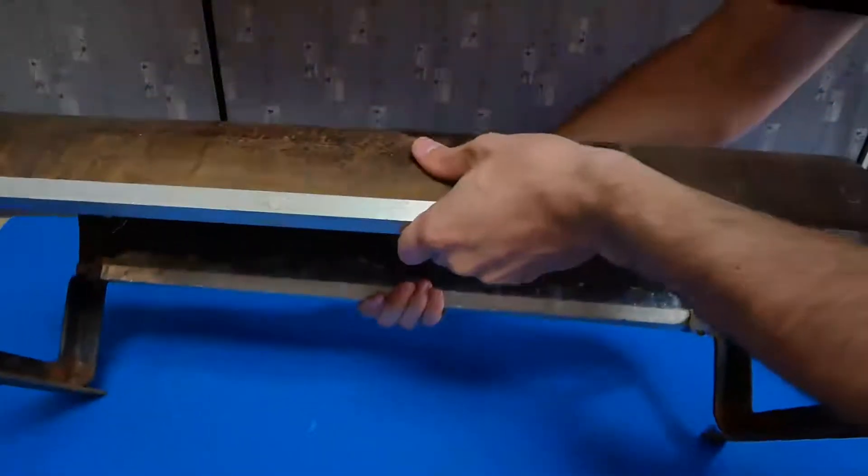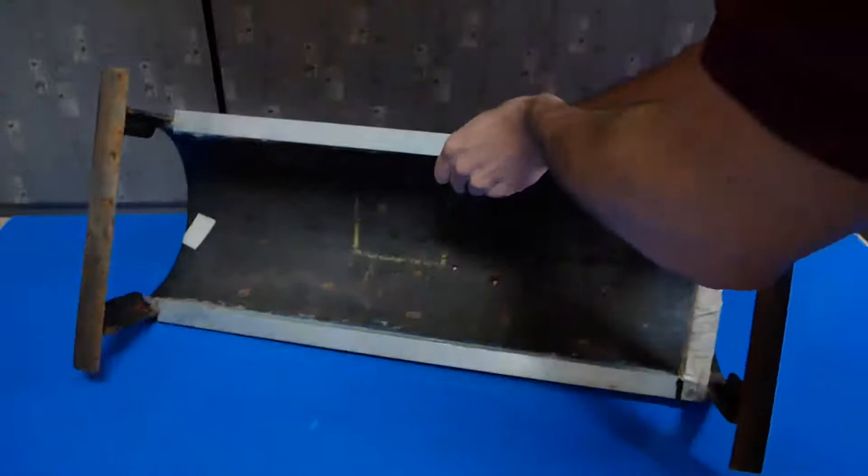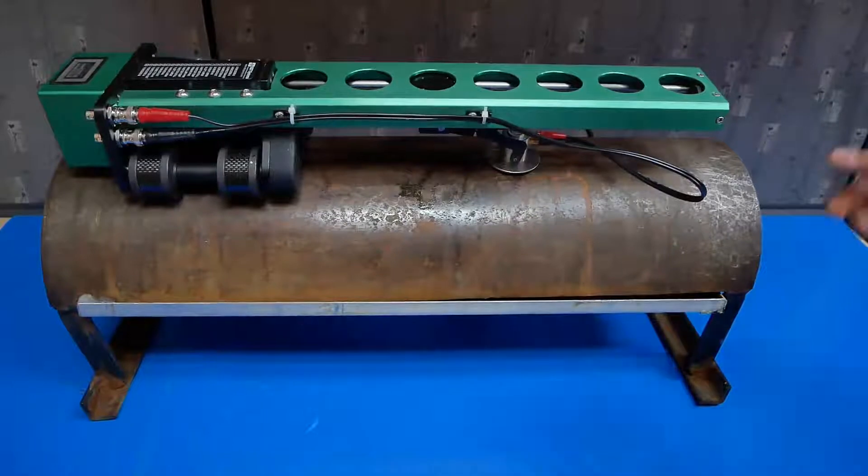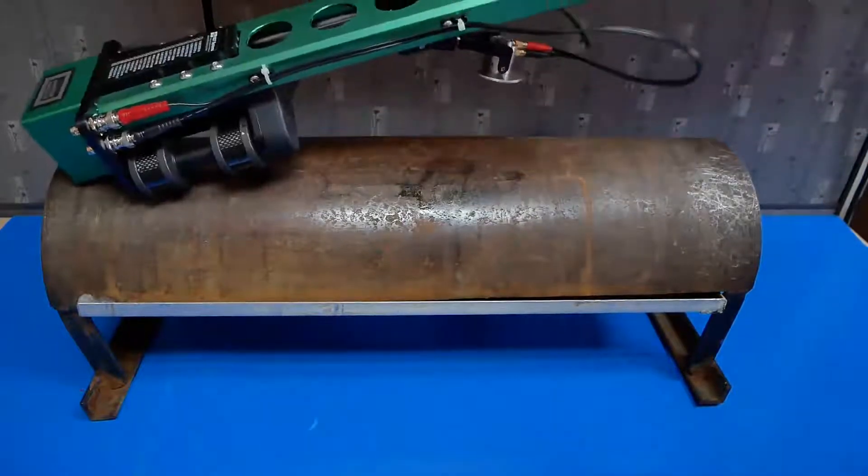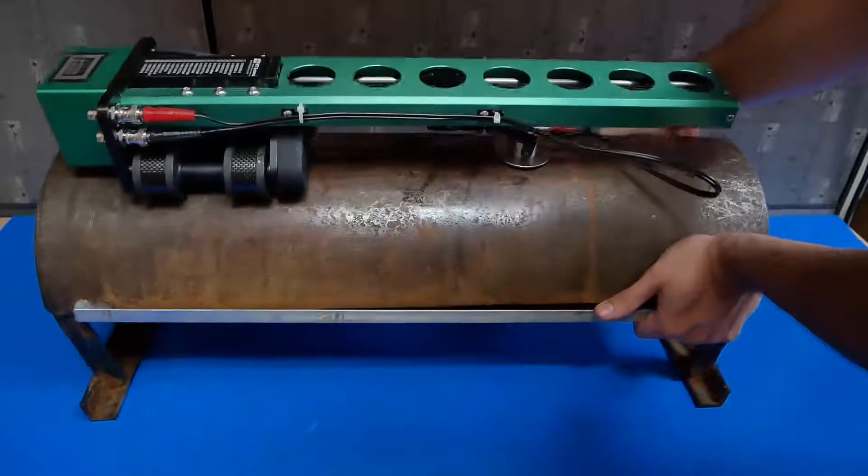The CIS is designed to measure corrosion on a huge variety of samples. The magnetic wheels cling to the circumference of your sample, and any pipe or tank 4 inches in diameter or larger can be inspected by the CIS.